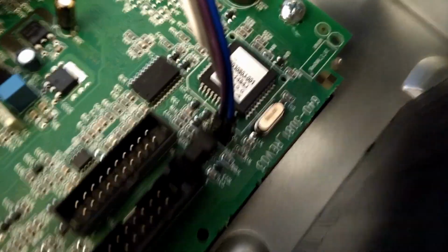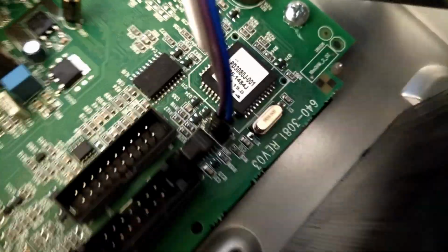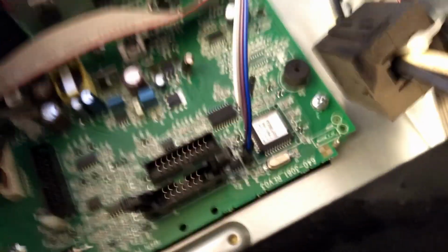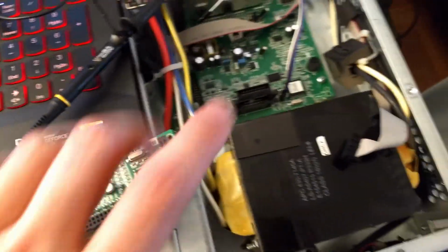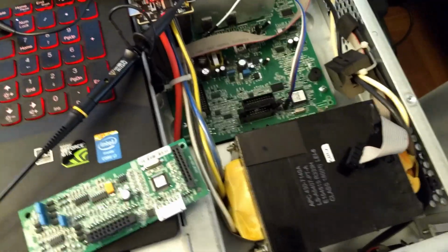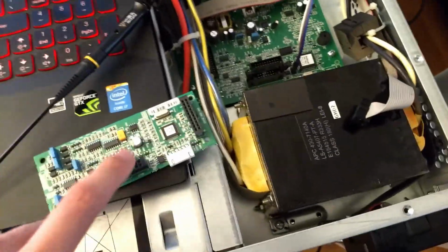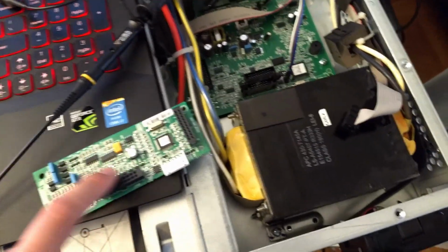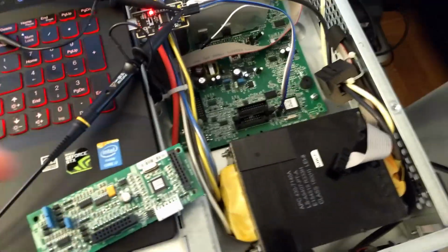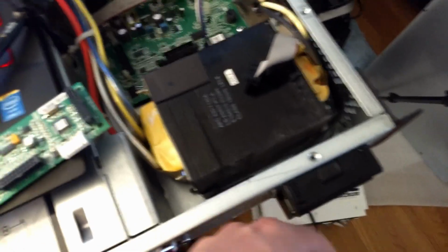And so these two modules internally still communicate using the APC smart protocol. So there's a programming header on the circuit board here, and you can see it's a 6-pin, and I'll give you the pinout for this in a moment. It is the serial interface between these two boards. So when this board's plugged in, if you hook up to it, you can see them talking to each other. This board every so often is sending requests, and the main processor is spamming back all that data, and that's how your front screen is working and is populated.